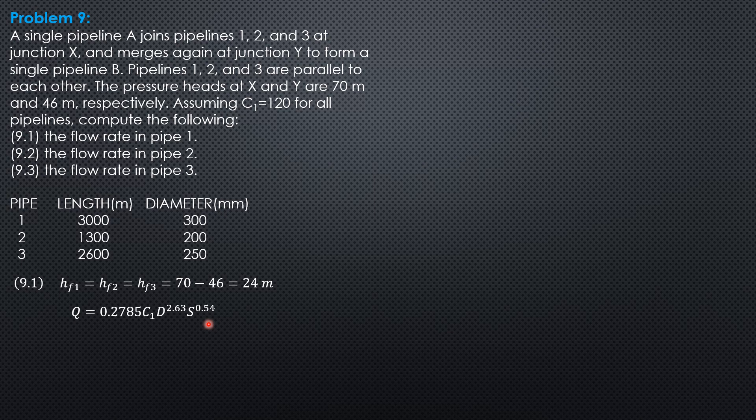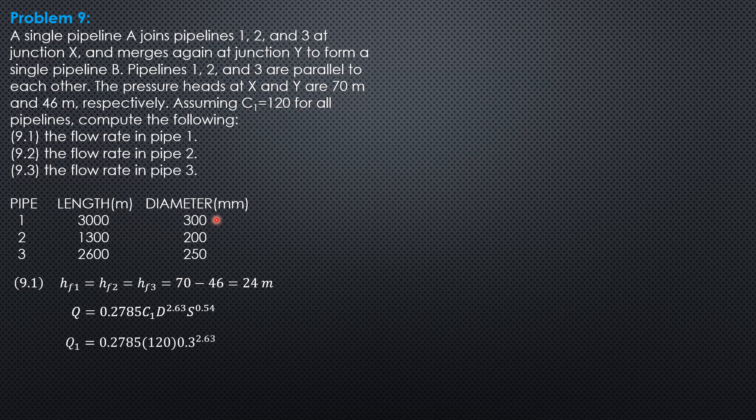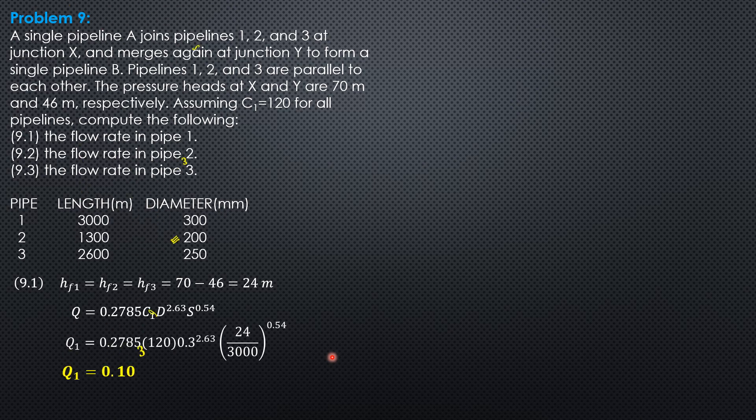So for pipe 1, Q equals 0.2785 times 120 times 0.3 to the 2.63 times quantity 24 over 3000 raised to 0.54. So Q1 can now be determined: 0.1039 cubic meters per second.